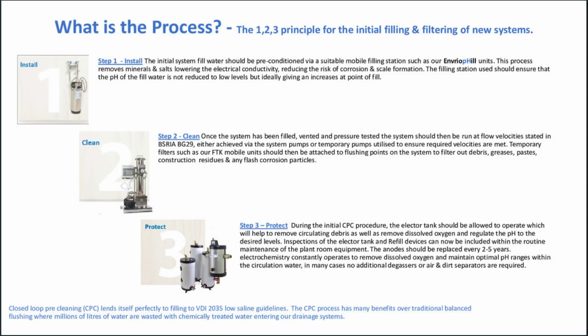So step 3 is protect. During the initial CPC procedure, the elector tank should be allowed to operate, which will remove circulating debris, as well as remove dissolved oxygen and regulate the pH to the desired levels. Inspections of the elector tank and refill devices can now be included within routine maintenance of the plant room equipment. So the anode should be replaced every 2 to 5 years. Electrochemistry constantly operates to remove dissolved oxygen and maintain optimal pH ranges within the circulating water.